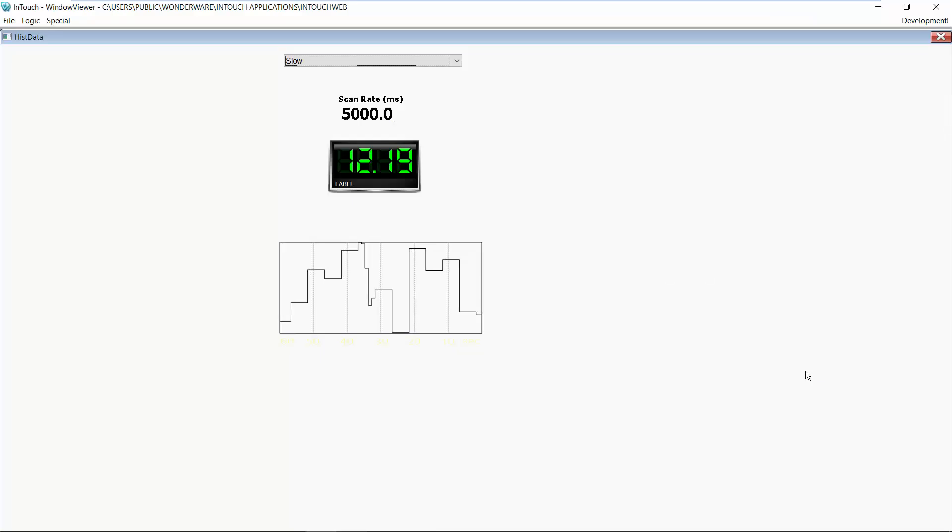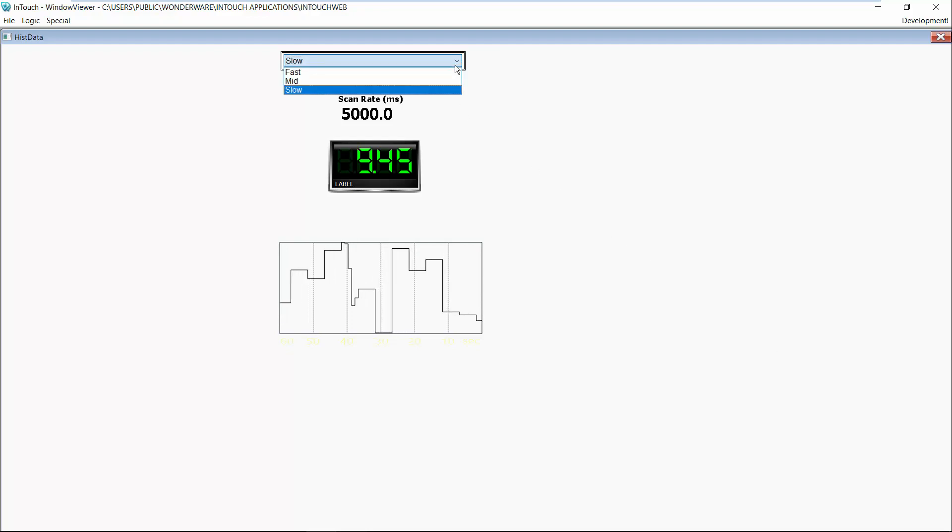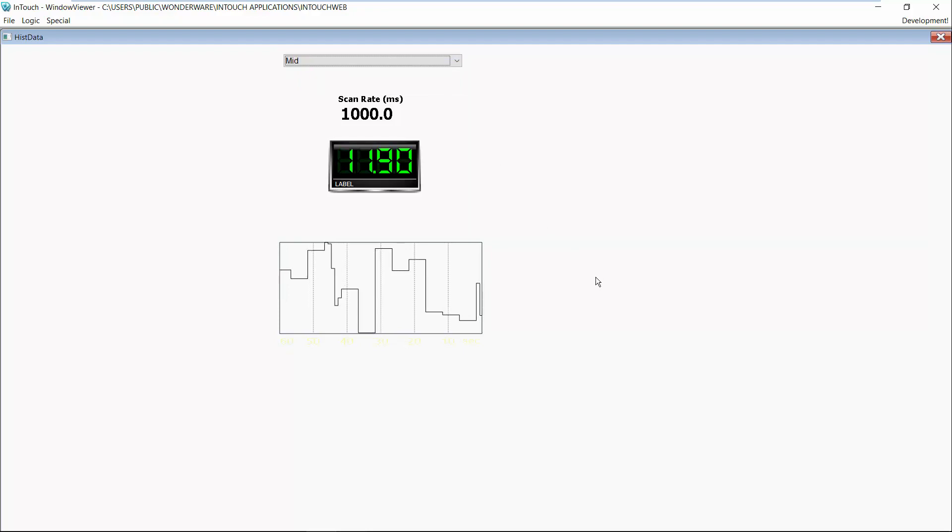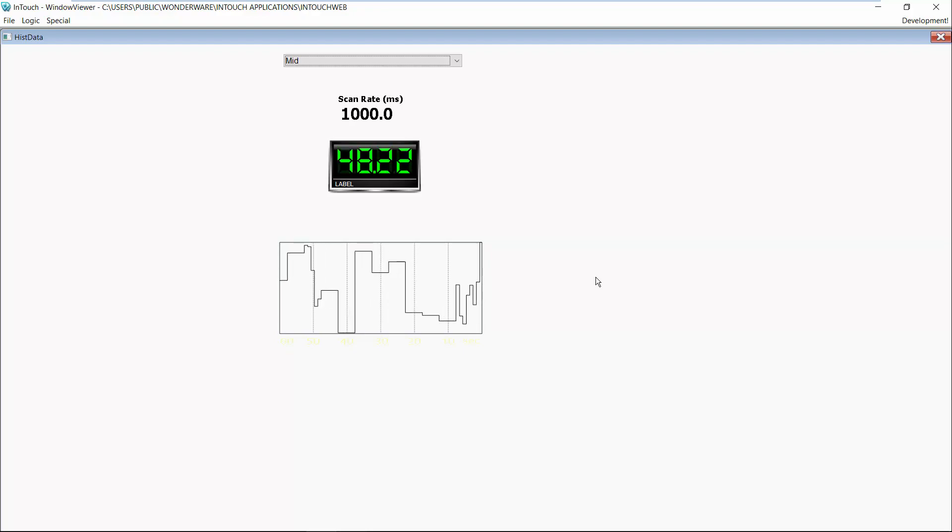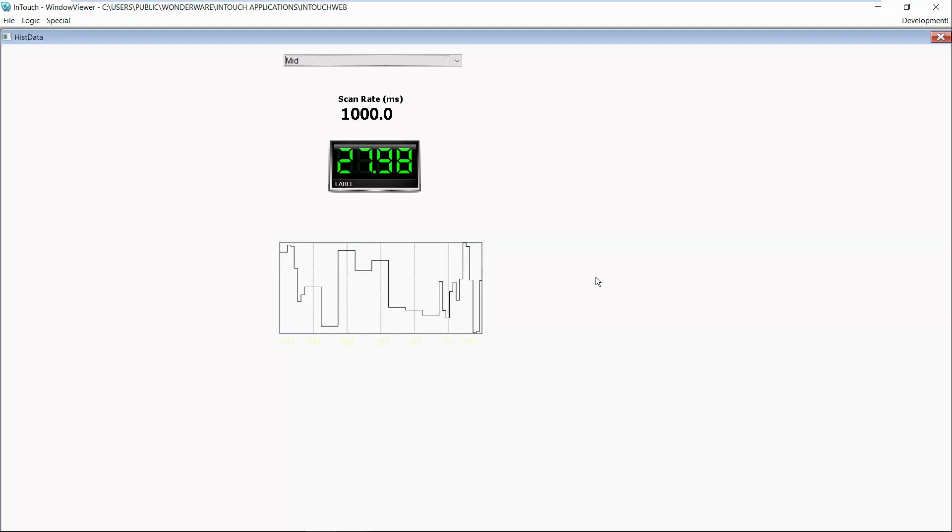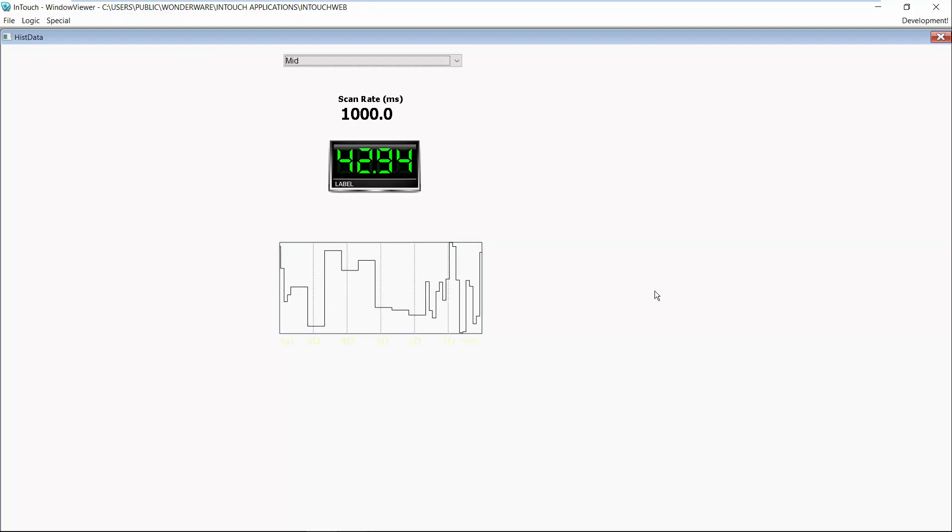So now we're going to go change that parameter at runtime to see the difference of the data being updated on the screen. So I'm going to change this to a mid-level which is basically a thousand milliseconds. As you can see the data is updating a lot quicker on my real-time display. The data is updating a lot quicker on my trends. So we're pulling the data from our PLC, in this case a simulator, at a one second rate which affects the display and affects how fast I'm logging my data to my Wonderware historian.